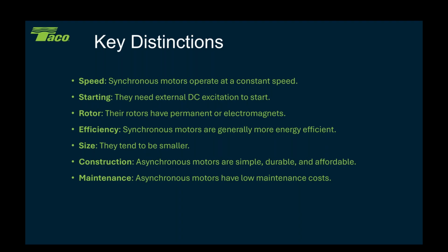Asynchronous motors are simple, durable. You know, they've been around forever. Everybody understands them. There's nothing real complex about them. Both motors are relatively maintenance free. You still got to maintain bearings. You still got to keep the dirt off of them. They're cooled by air. So none of those things change any. The big difference is in the starting technology and the way the rotor is built.